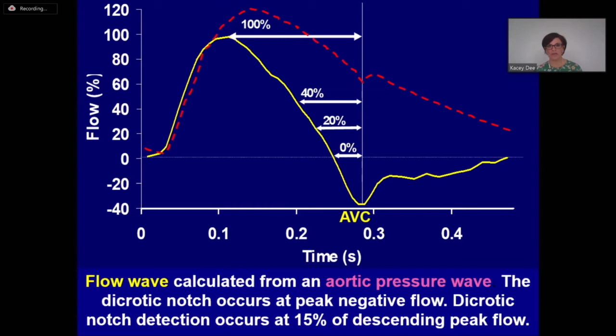This diagram here gets a little bit strained on the eyes, but it shows the method used for calibration of the flow wave. Under normal non-assisted beats, in that top left graph there, the beginning and end of systole are determined, and the red marks on that waveform show you those points. And on the flow wave right below, at the point of the aortic valve closure, the flow is brought back to zero, and this will be used during the assisted beats to predict the pressure and flow without augmentation.